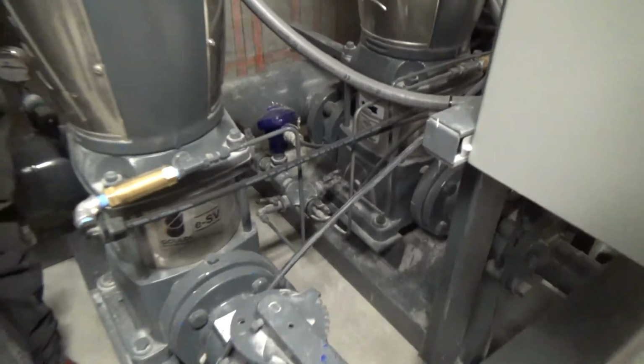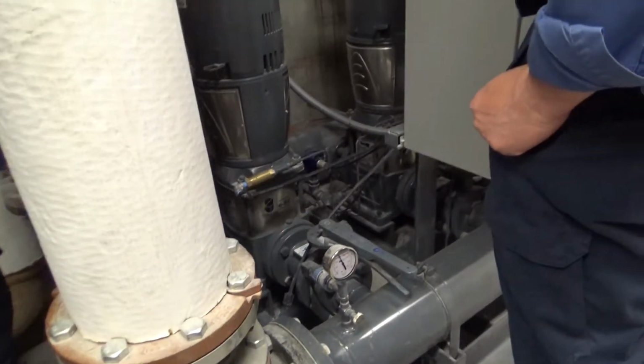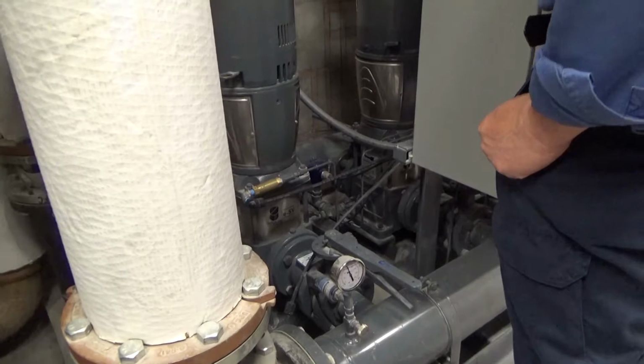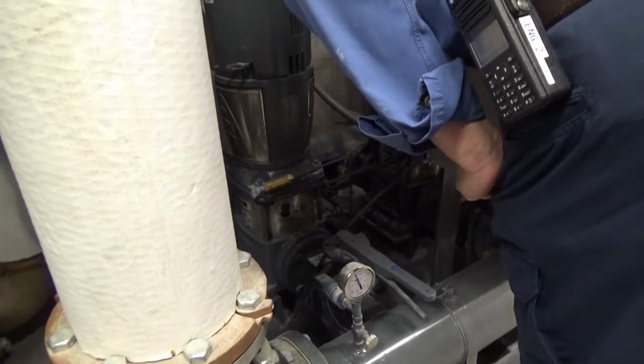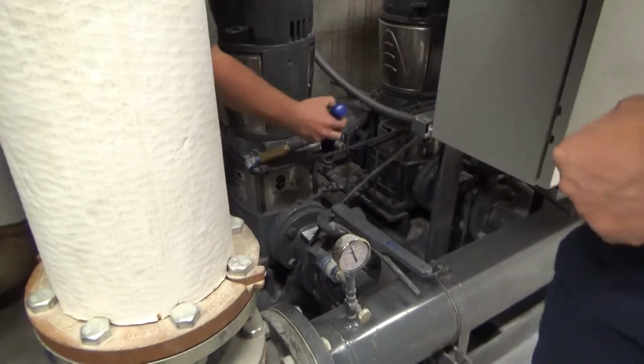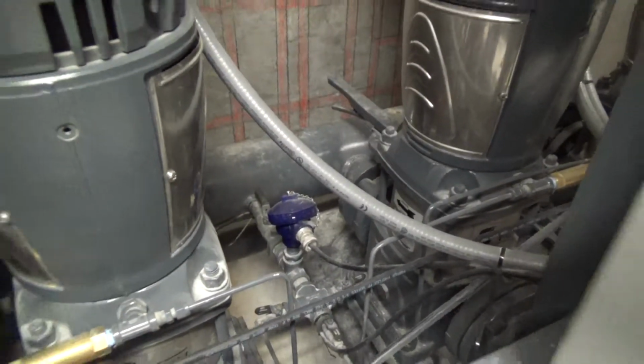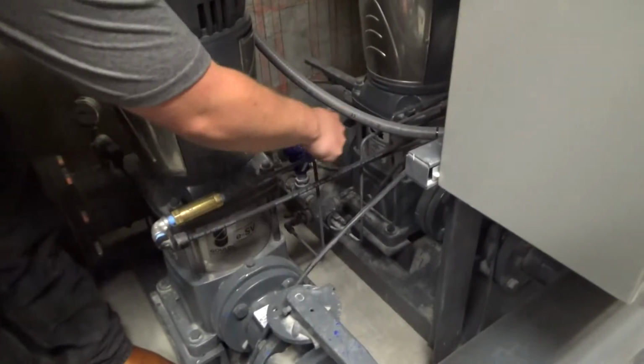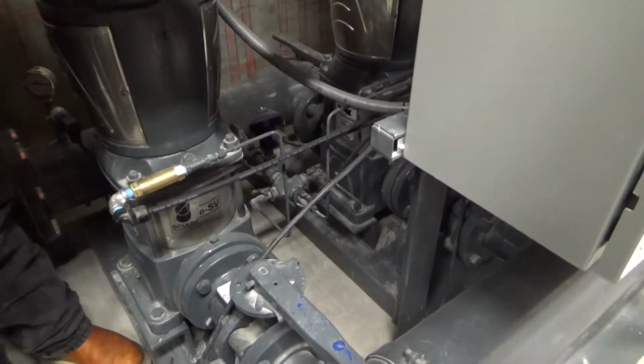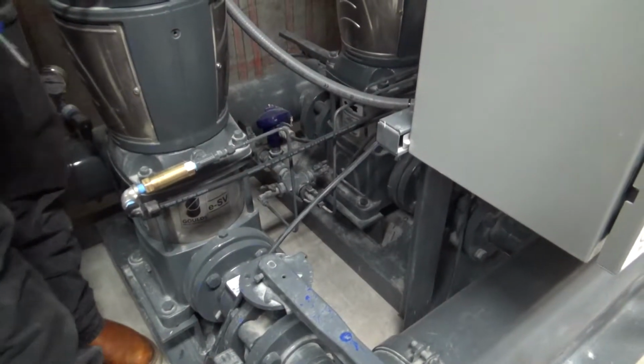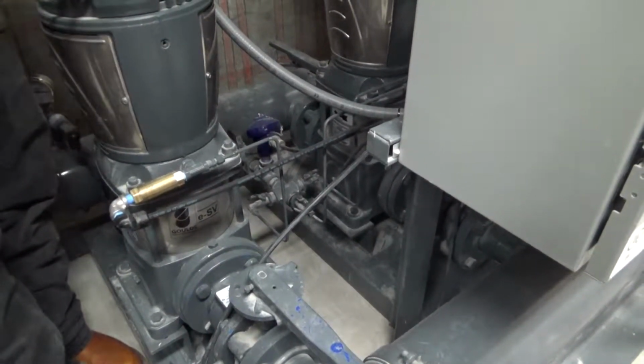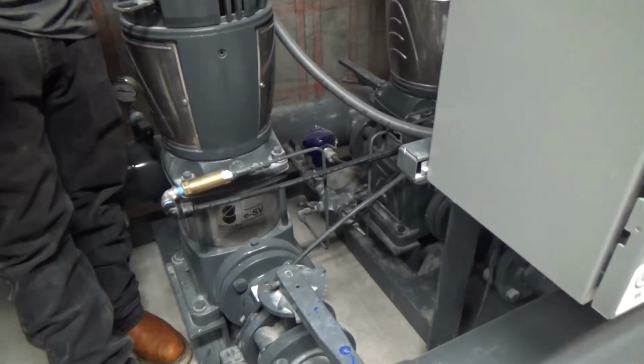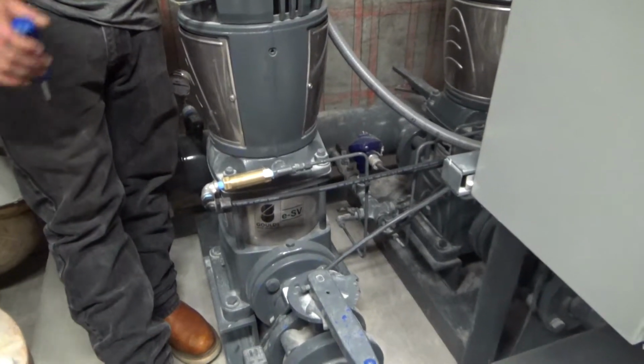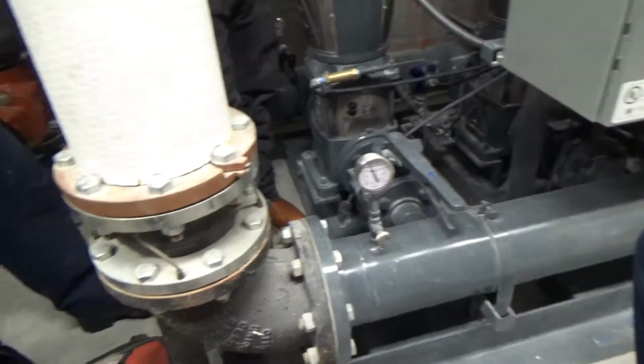What that is, we call that the no-flow header, or the no-flow manifold. That's part of that temperature sensor that I was talking about earlier. That's what that blue head is, so that's that temperature sensor. The reason it's all piped, it has all these tubings, is it's taking the hottest water from where that seal is, which is what we're trying to protect, and sending it right to that sensor, from every single pump. So the hottest water is going right to the sensor, and the panel's looking at it and saying, okay, as long as you're under 100 degrees, we're good. Oh, you're over 100? All right, I need to start shutting things down before we start ruining seals.